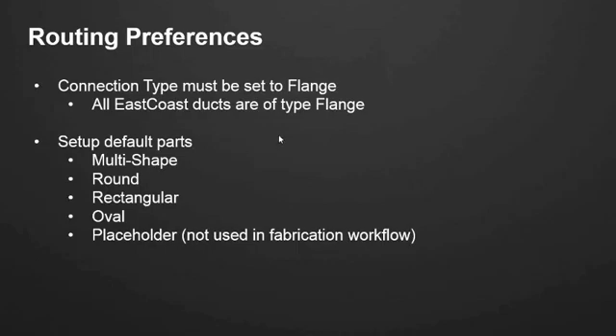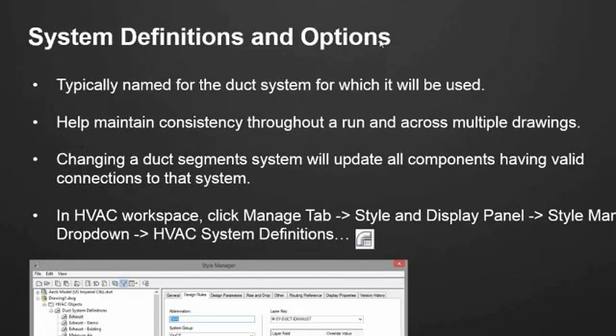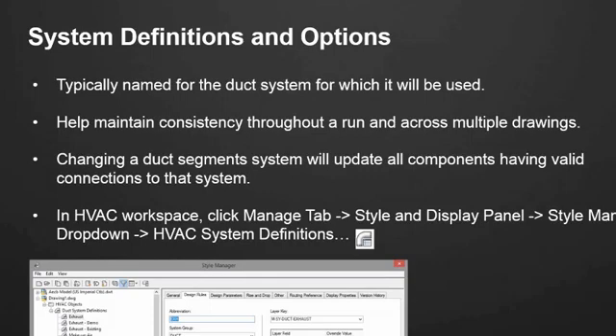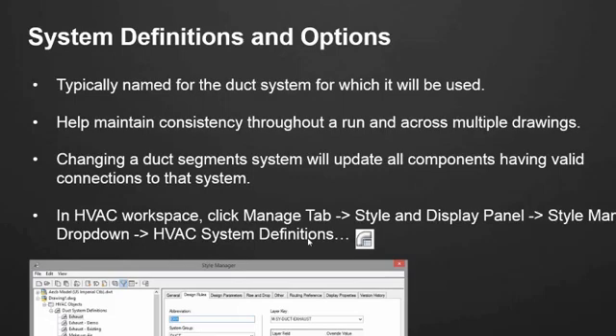So the last thing that I want to talk about today is the system definitions and the options that they offer. A system definition is typically named for the duct system for which it will be used. You're not going to name a system definition return and then route supply with it. So you would name it typically for the type of system that is going to be contained within your duct. System definitions help maintain consistency throughout a run and across multiple drawings. And what I mean by that is in the same way that a routing preference chooses what parts you're going to use in your design, the system definition really decides how those parts are going to look. It sets your layers, your display style, how your lining will look, how your insulation will look, all of that sort of thing. And you access it in the same way that we found the routing preferences.